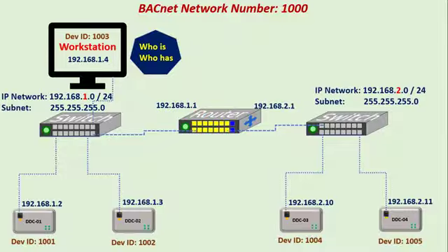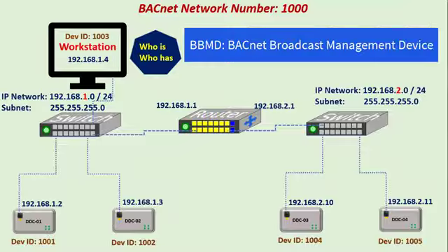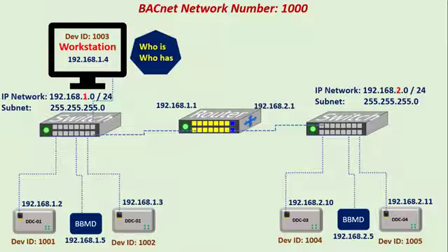To resolve this issue, the BACnet standard introduced the BBMD, or BACnet Broadcast Management Device. A BBMD must be present on each subnet. It is not necessary to purchase a separate BBMD. Usually BACnet IP routers and building controllers support the BBMD functionality, and we can configure BBMD functionality in these controllers or routers.